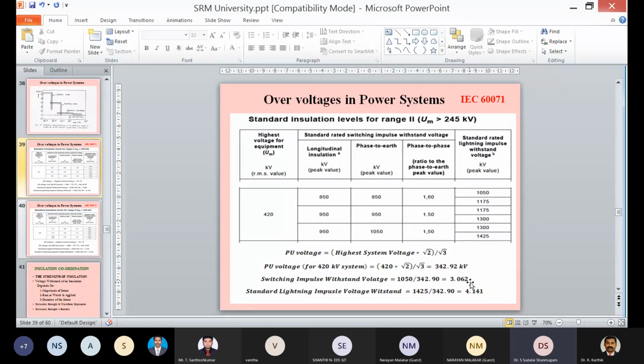It literally says your switching impulse voltage level is 3 times the per unit level actually here. Okay. The standard lightning impulse withstand voltage is equal to 1425 divided by 342.90, which gives 4.141. You can see now, when the system voltage is above 400, both are coming closer. This is 3.062, this is 4.141. I'll just give 1 minute to observe this, then I'll move to the next slide.